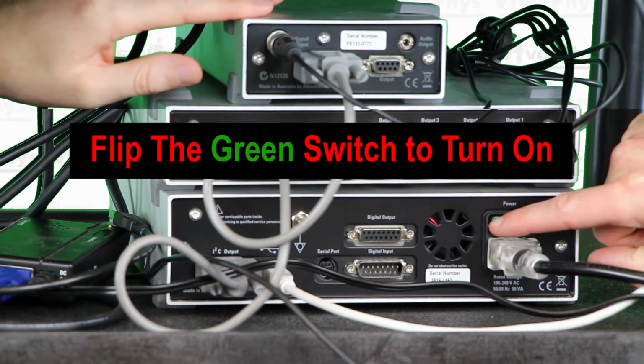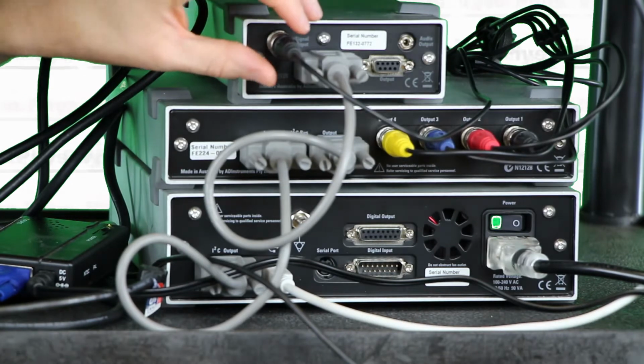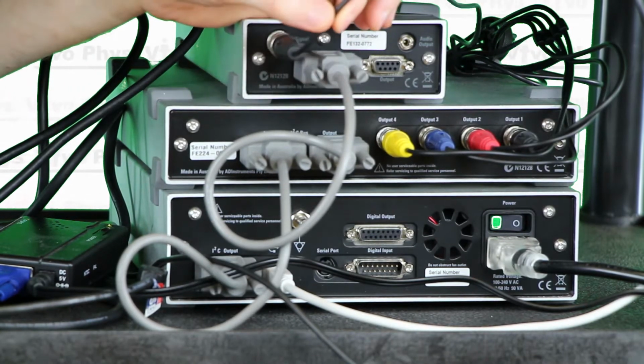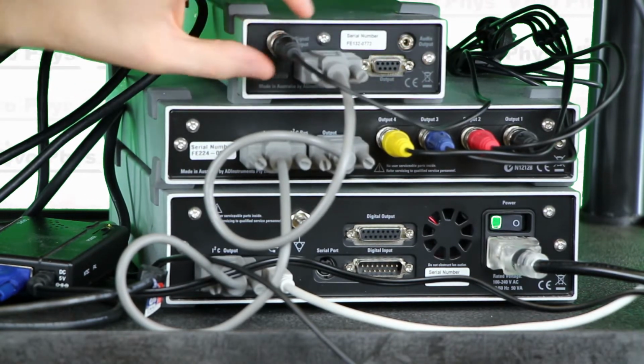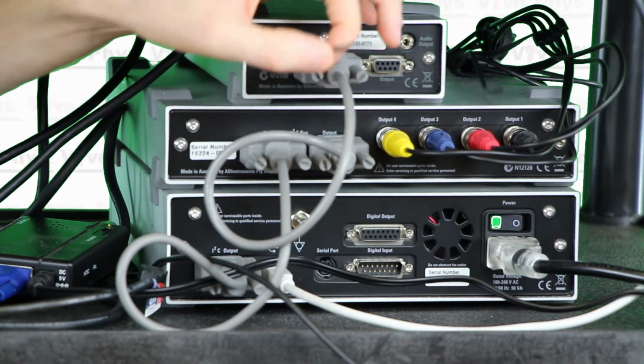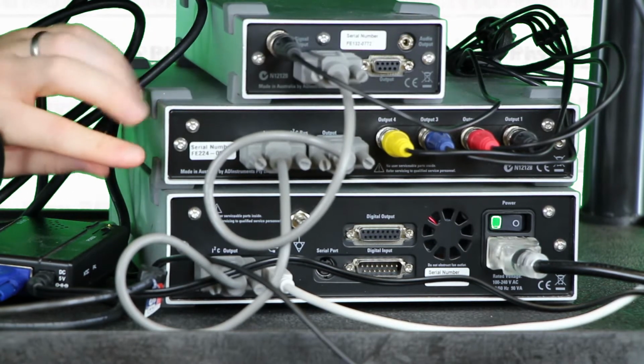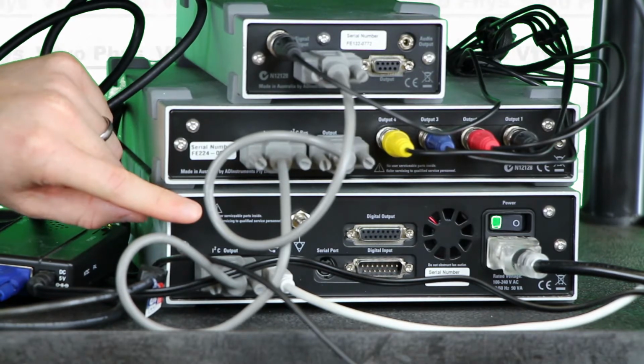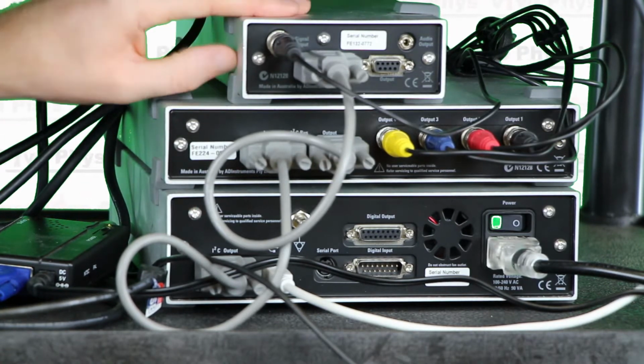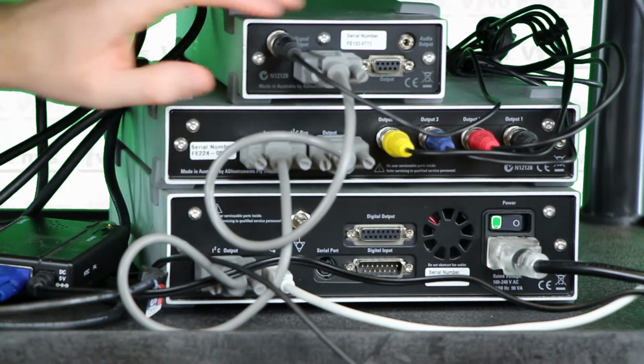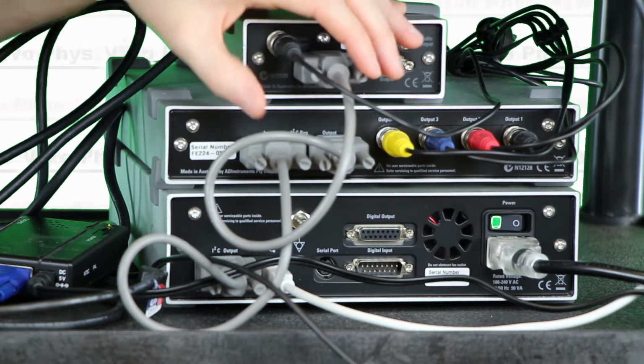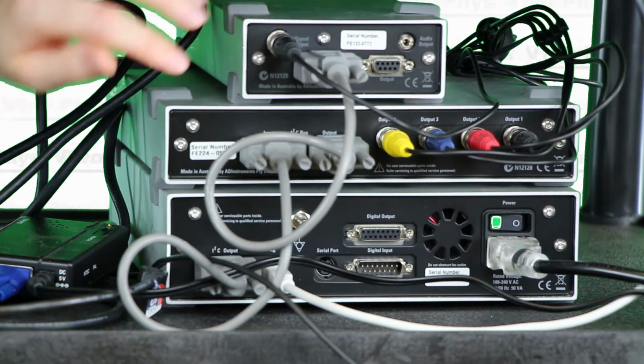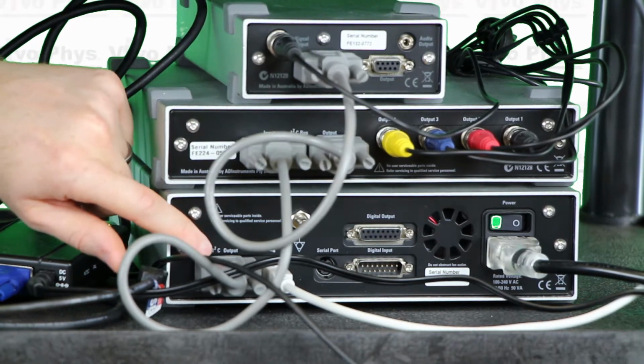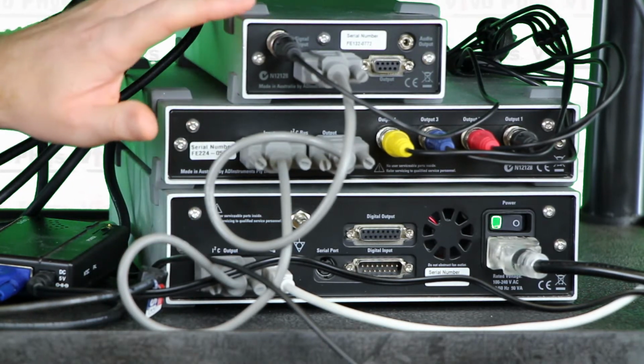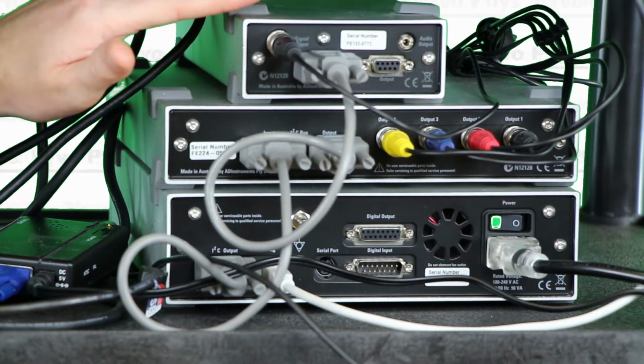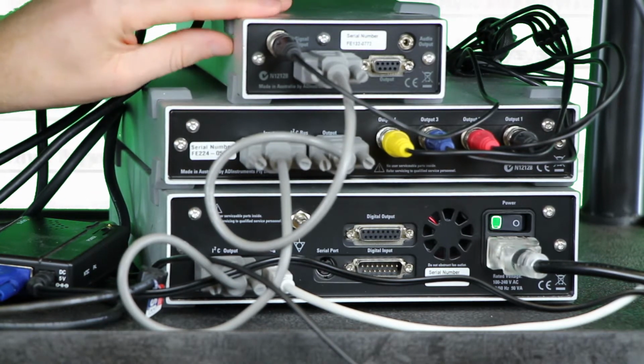So we have the PowerLab already on, and we have this black BNC cord here plugged into the back of the bioamp, and that's plugged into one of the BNC outlets on the front of the PowerLab. And that's how the information is going to get from the bioamp to the PowerLab. We also have this series of gray cords here going from amp to amp to eventually the PowerLab system right here. And that is actually the power cord that is going to give power to this bioamp.